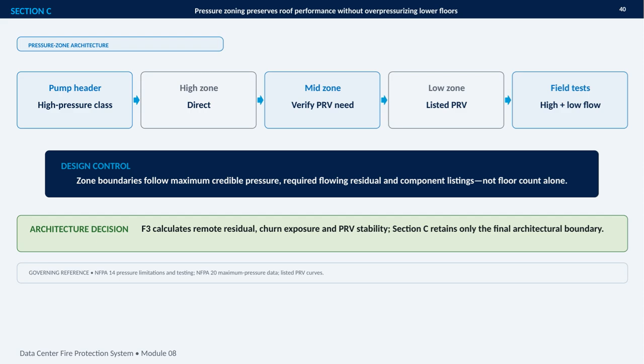The zone boundaries are based on engineering conditions, not simply on the number of floors. They must account for the maximum credible pressure, the required flowing residual pressure, and the listings of the installed components. The high zone may connect directly, while the mid-zone requires a review of whether a pressure-reducing valve is necessary.